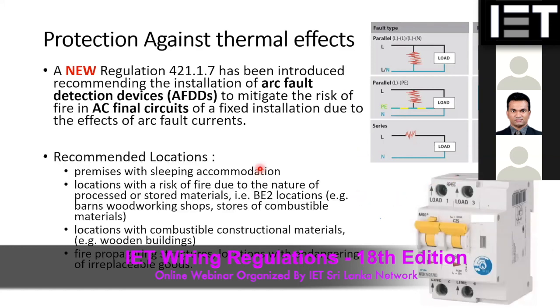As per the new regulation, there are certain locations where the regulation recommends having arc fault detection devices as a compulsory requirement, like sleeping and accommodation locations, for example hotels and those types of locations. It's recommended to use arc fault detection.